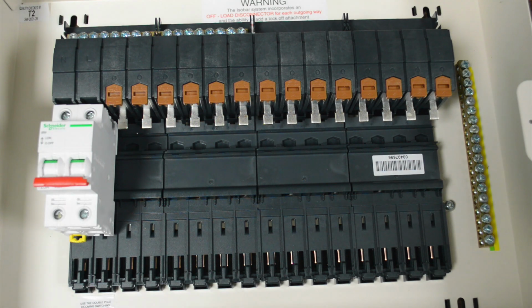So in front of us here we have got a Schneider Type A Acti9 distribution board consumer unit. This is typically what you would find in a commercial installation, and the reason for that is generally to do with the higher prospective fault currents you'll be expecting to see at locations where the distribution equipment is needed. So as we know, with our consumer units typically used in domestic environments, they're not really rated in a way that would be suitable for a large majority of commercial and industrial installations.